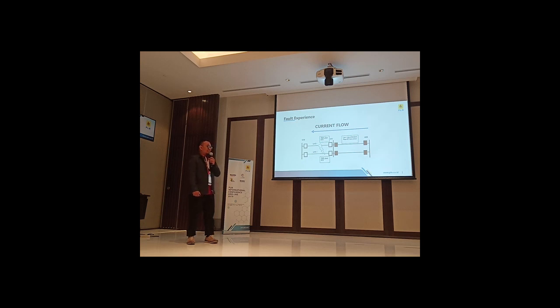But unfortunately, something happened in substation B and substation C. There was a line one trip with the indication trip differential, then after that a reclose. Actually, the fault is happening here, but why does this section have a response to the fault that happened in this area? So we must think about this.